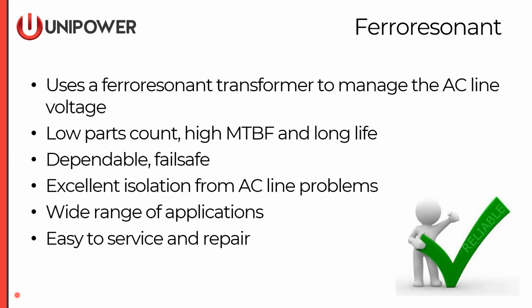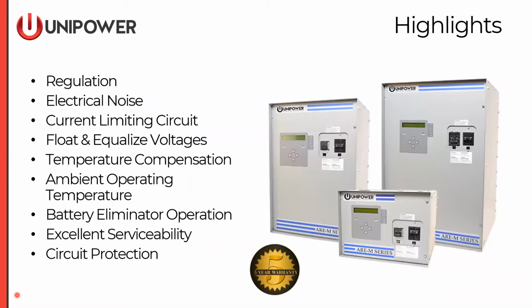John Rambin is going to open the front of these and show you some pictures of what the inside of one of these units looks like and how we service and repair them. Again, a Ferro Resonant is a very highly regulated unit, low in electrical noise, and just like any battery charger, we can limit the current. There is a microprocessor control board in here, so it does achieve its regulation through physics, but we do control the tank circuit with a microprocessor. It offers temperature compensation, which is a common feature on battery chargers, especially in utility applications.